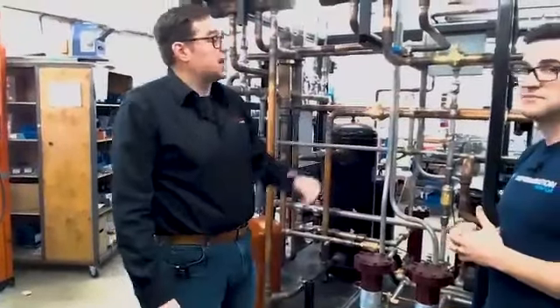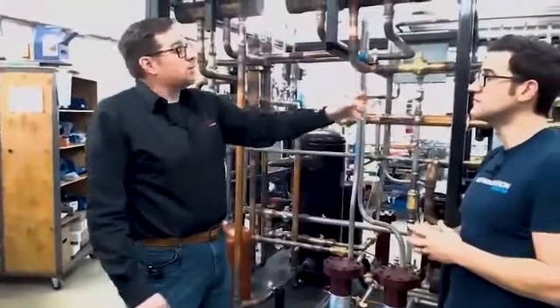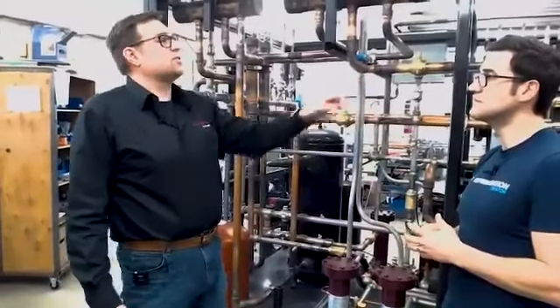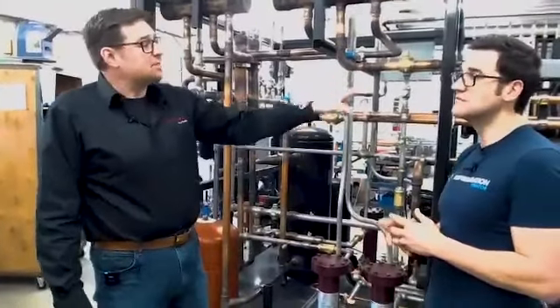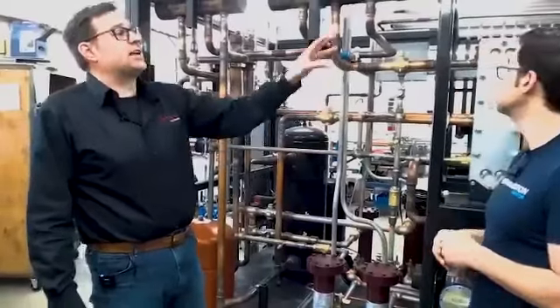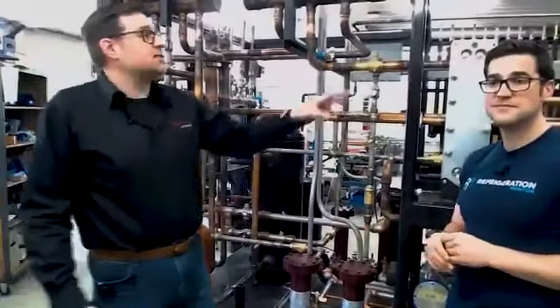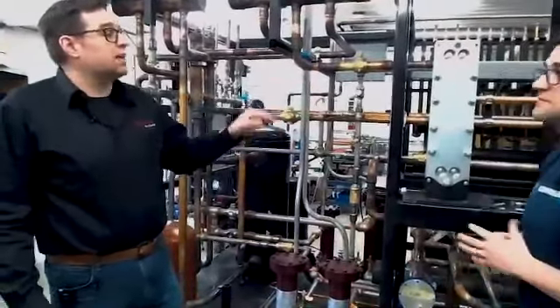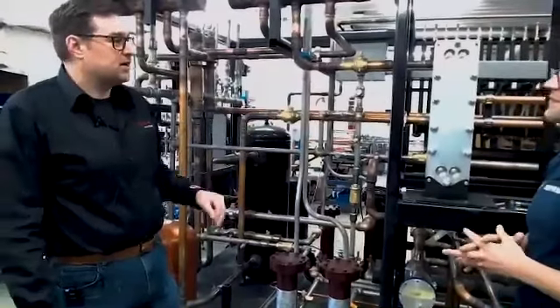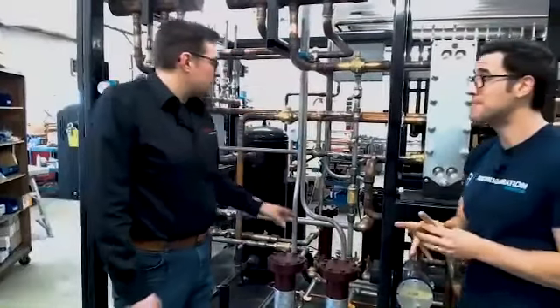We're either going to do some flash gas subcooling, or afterwards, we'll go through a high pressure expansion device and go into a flash tank. This application here is slightly different because we have an intermediate vessel to maintain a certain column of liquid that we need for a flooded evaporator. But the principle always remains the same.